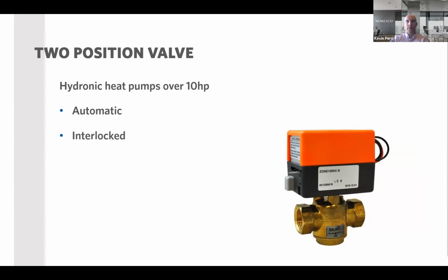Okay, 2 position valves. With this section, hydronic heat pumps over 10 horsepower have to have these 2 position valves now. And what that is basically is that the automatic valves shall be interlocked to shut off the water flow when the compressor is off. So it needs to be automatic and interlocked. Probably not a big thing, but it might add a little bit of cost to the project, but this is good practice anyway.